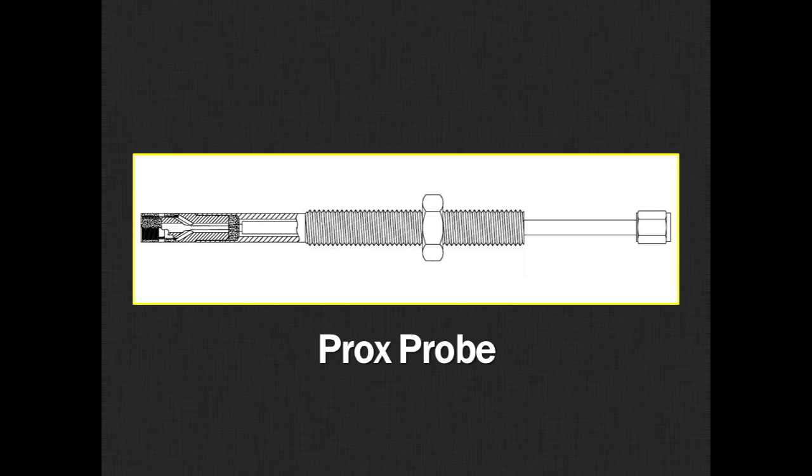Here's the typical probe. It's the tip we just showed you mounted in a stainless steel body. This is typically a 3/8-24 thread for many machines. Coming out the back we have a coaxial cable and a connector on the end so we can hook it up to the electronics.